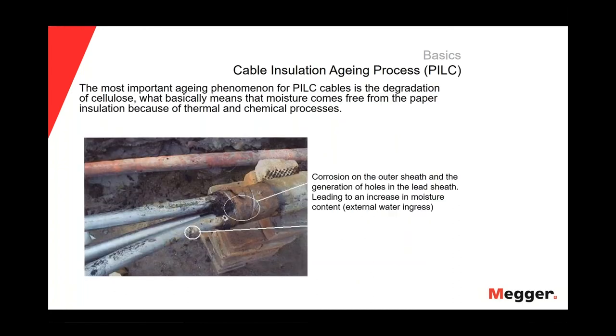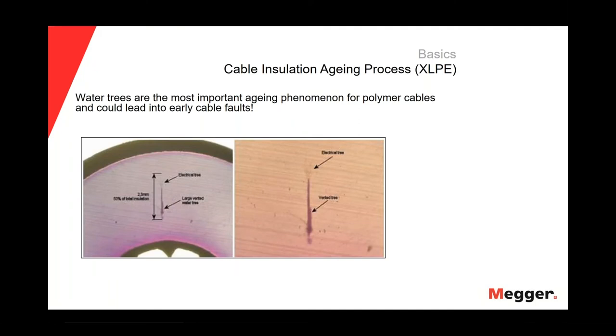Regarding the cable insulation aging process for paper impregnated PILC cables, the most important aging phenomenon is the degradation of the cellulose. What basically means is that the moisture comes free from the paper insulation because of thermal or chemical processes. Of course, the corrosion of the lead sheath and the generation of holes in the lead sheath will lead to an increase of the moisture content, okay? That's in the case of PILC cables. Regarding XLPE cables or polymeric insulation, by far the water trees are the most important aging phenomenon for polymer cables, and could lead to early cable faults, okay?